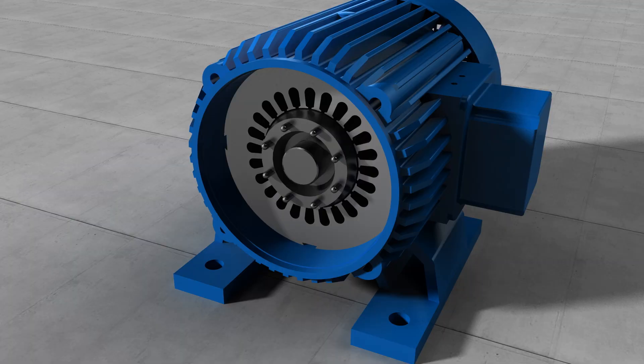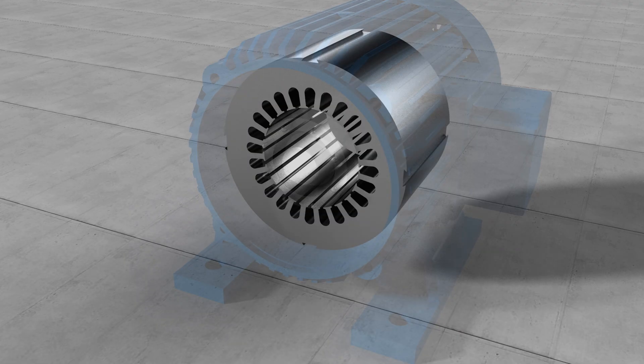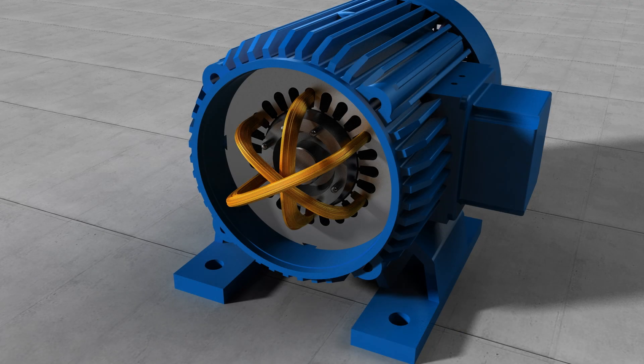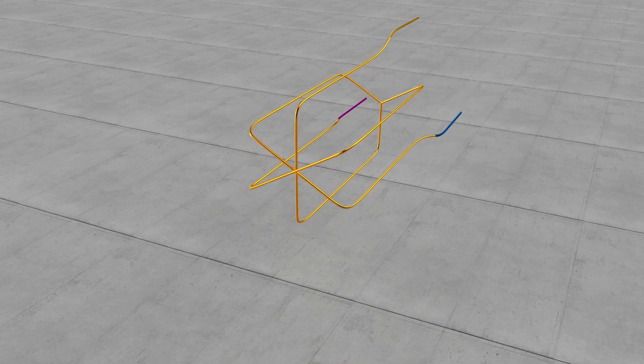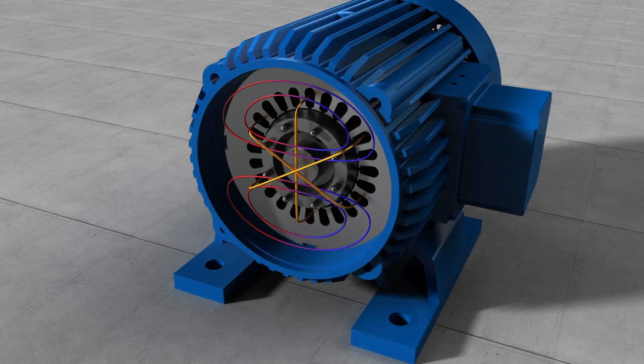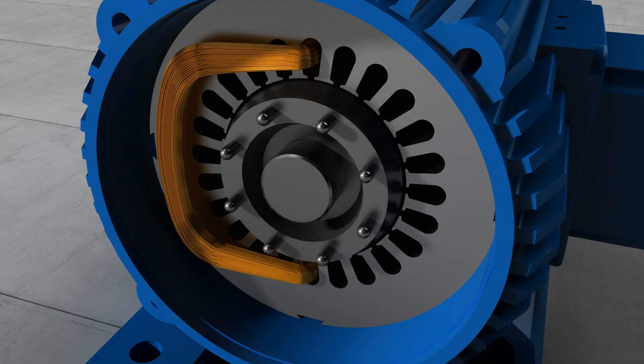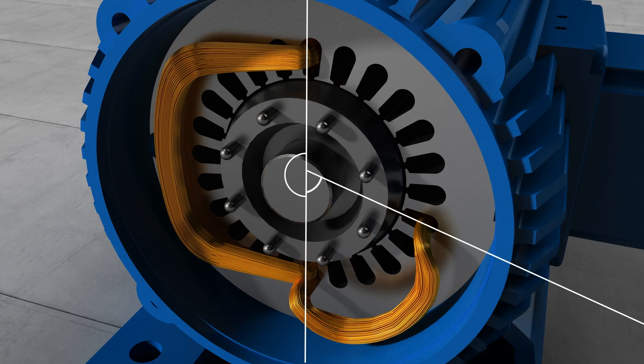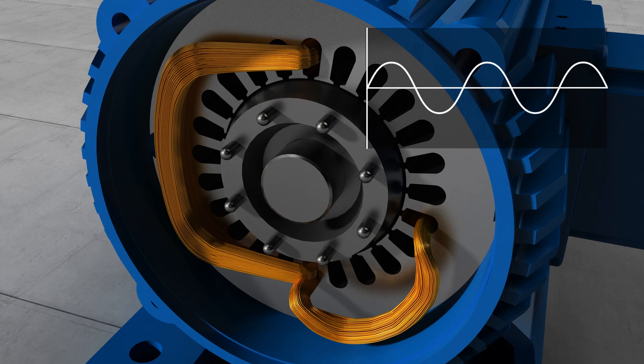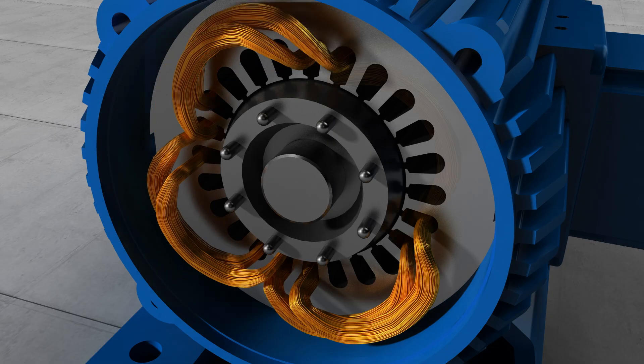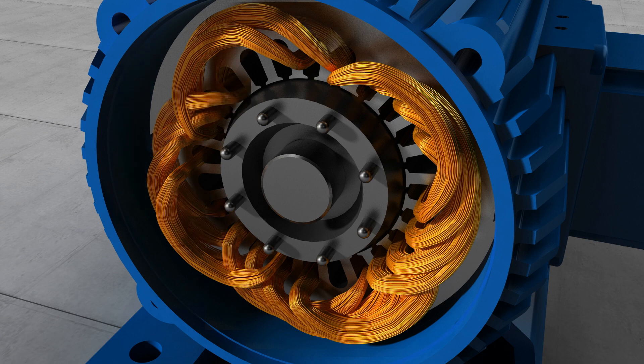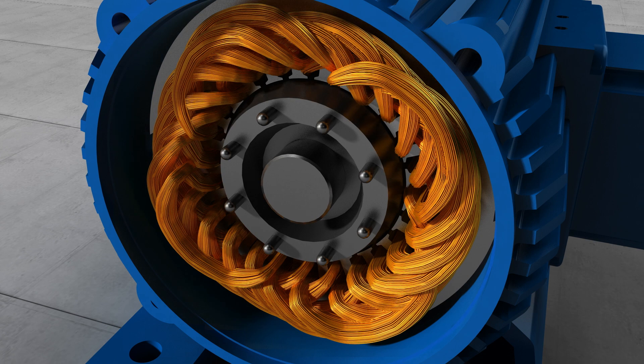Here is a three-phase induction motor. The main components are the stator and rotor. A stator is the part that produces the rotating magnetic field, and a coil is wrapped in the slot. The three-phase current each goes in and out respectively, and with such movement a rotating magnetic field arises. As the number of coils increases, so does the power of the magnetic field. Usually, the angle at which coils are placed apart from one another is less than 180 degrees, because you can effectively save the number of coils used, making it economical. The waveform created from such an angle is also easier to manage. Although electromotive force decreases and torque value drops with a smaller angle, the advantages outweigh the disadvantages, and therefore this form is commonly used.